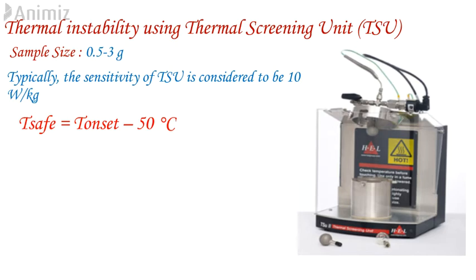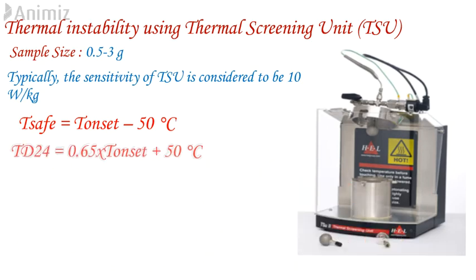Adiabatic decomposition temperature can also be determined from TSU, as TD24 = 0.65 × T-onset + 50°C. If TSU shows an onset of decomposition that is very close to the operating temperature, then it is better to perform adiabatic testing like ARC or PHITECH to confirm the exact onset of decomposition before taking appropriate measures.